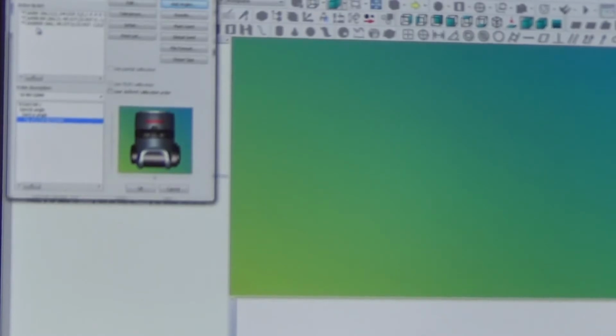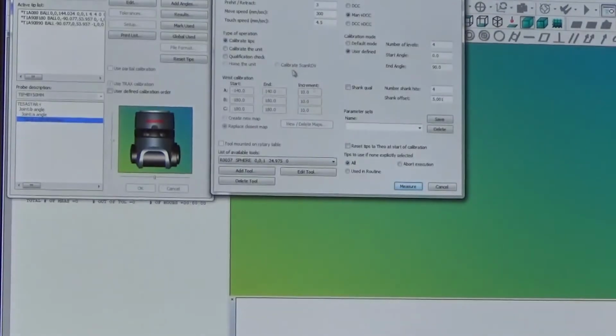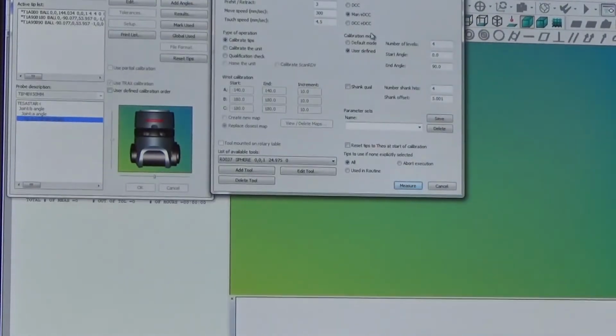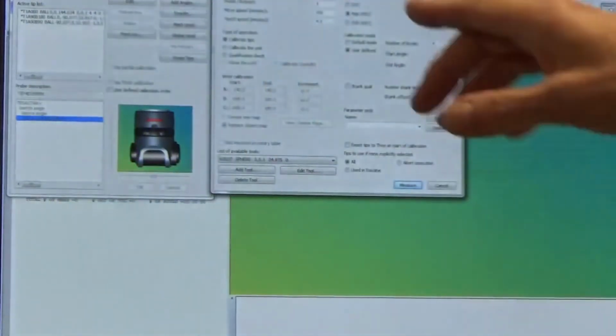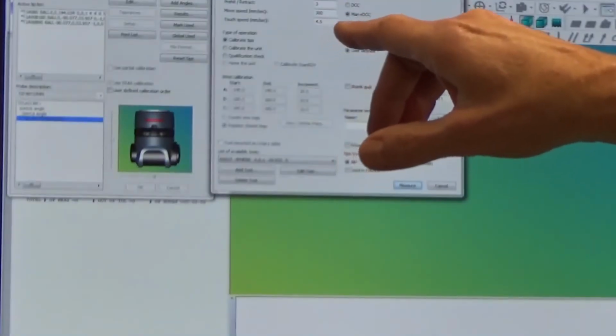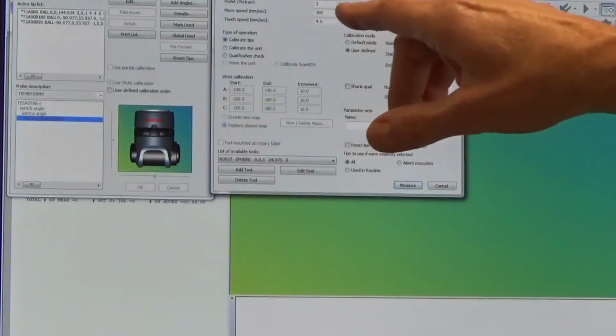Now what we want to do is actually perform the calibration. So we're going to come up here to measure, and we're going to take a look at some of these probe pieces of information. Number of hits is 13. That means it's going to take 13 hits around that ball, and it's only going to come down to about halfway. So if this is the ball, it's going to touch it on top, and it's going to work down to about halfway through, and it's going to work around the probe, and it's going to make a number of different levels. So what we have here are pieces of information around that.